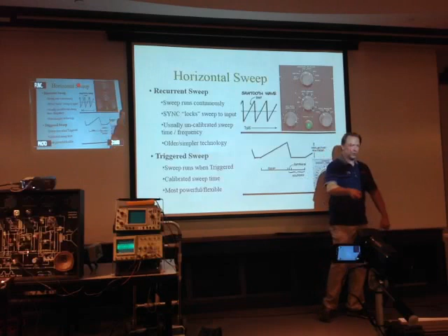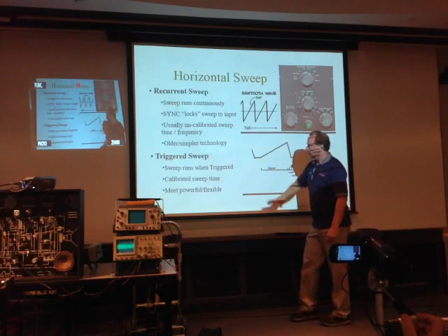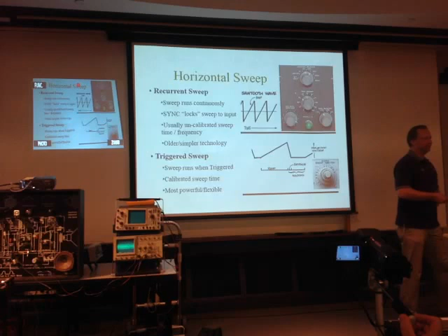Okay, so the trigger circuit says, send the sweep now. And then it goes back and sits and waits for the trigger again and sends it again. Okay, so if we give it a trigger that's synchronous to your signal, now the waveform is stable. So that's what we're talking about. We're going to talk about trigger here in a moment. But they generally have a calibrated sweep time, and they're more flexible and powerful than the old recurrent sweep scopes.